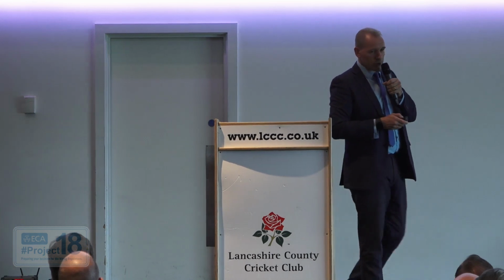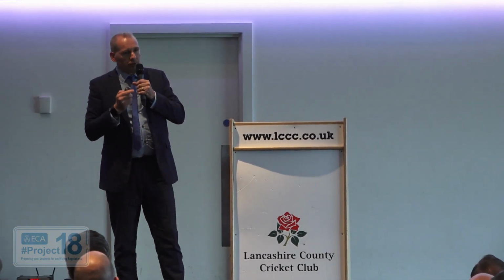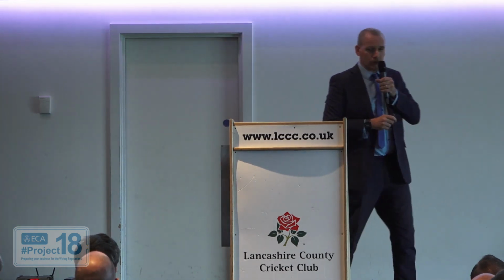So, just wrapping that bit up there, it just says it there, it's a significant change. It applies throughout the installation and not just in escape routes. So this new edition says that if you are using metal containment systems, you completely comply with this edition, completely, no question. It also says that it now precludes or doesn't allow the use of plastic clips, clamps, ties, or even non-metallic cable management systems if they're the sole means of support.